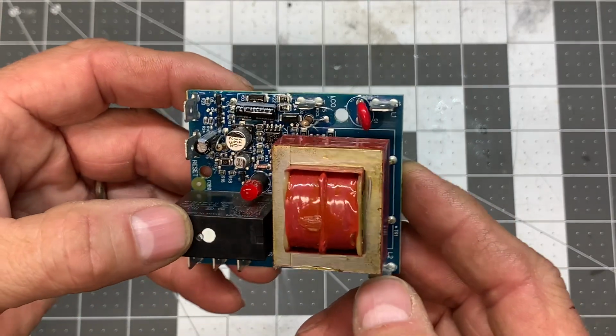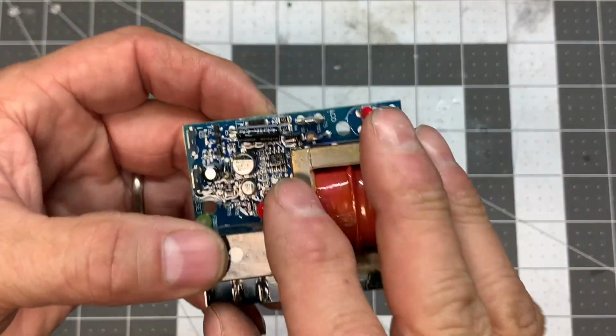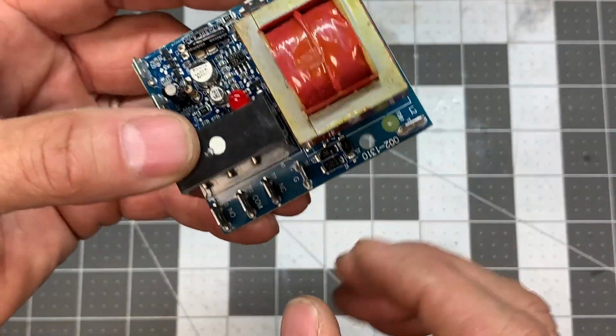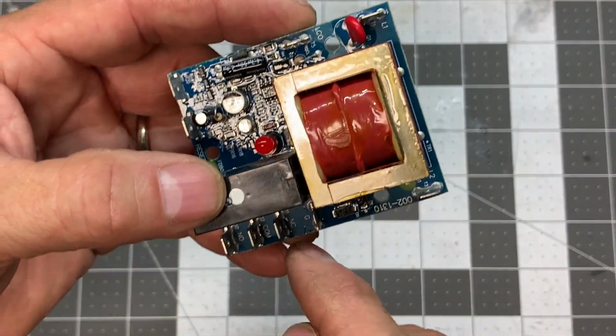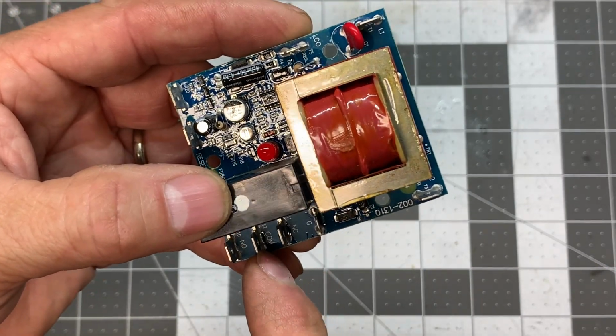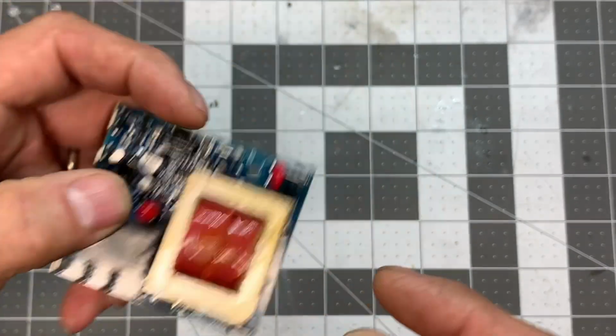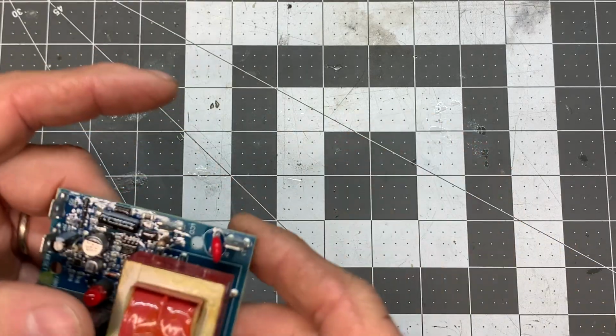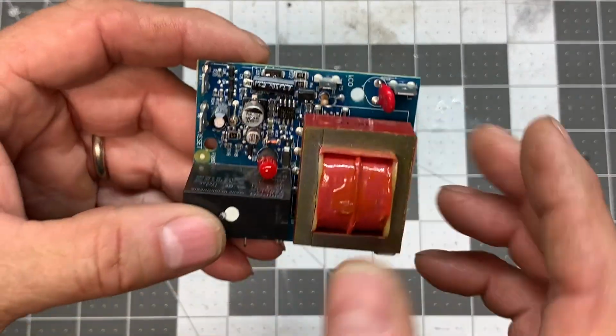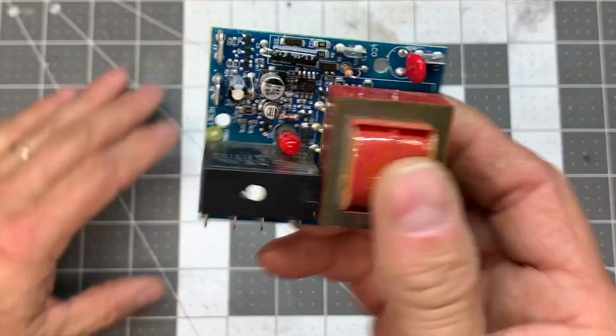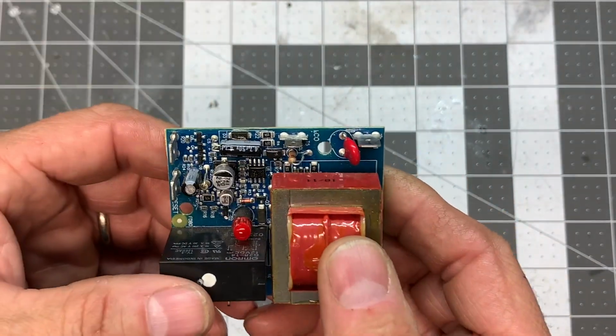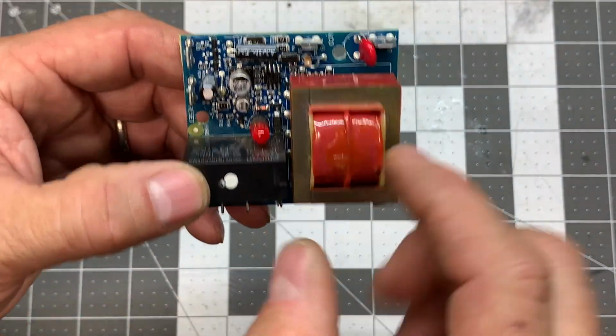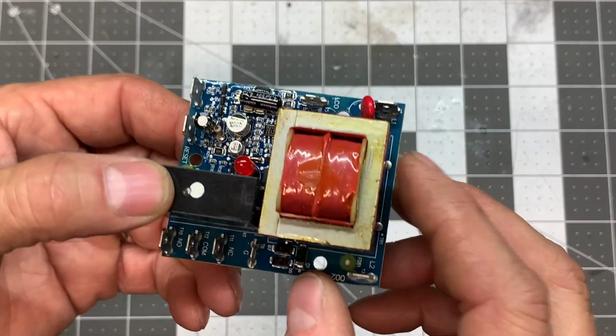So one workaround temporarily to confirm that this board is bad is to just take the common terminal and the normally open terminal and short them together and then fire the boiler up, and the boiler will run. Well, then you know that this circuit is bad. Either the probe is bad or this circuit is bad. So we're going to see what happens here.